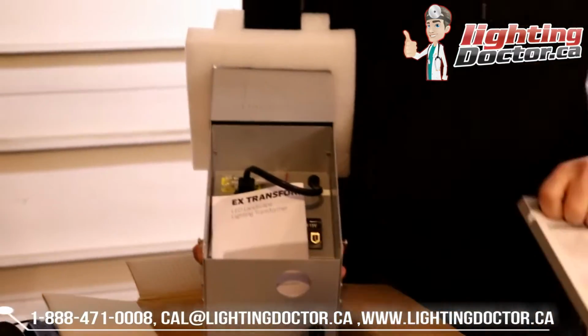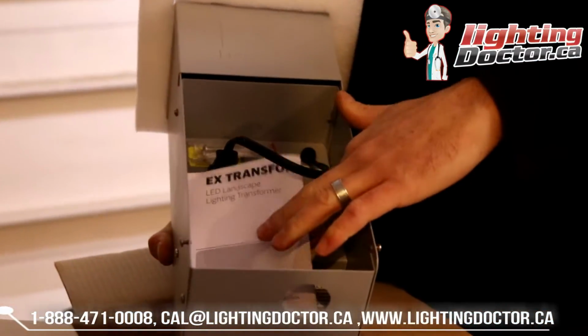So again, if you had 10 of these at 5 watts each, now you're at 50 watts. And say you had 10 more at 2 watts each, that's 50 plus 20, so you're at 70 watts. You'd want a transformer that's probably 100 watts or more to operate that system. It's really easy to calculate out.